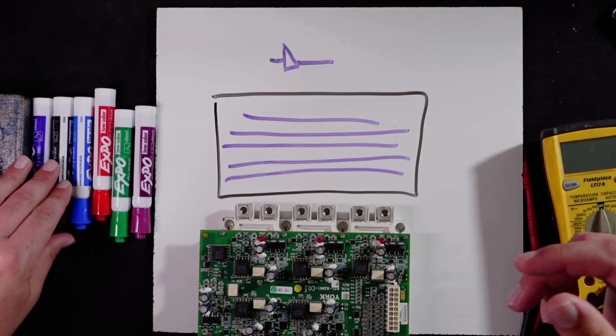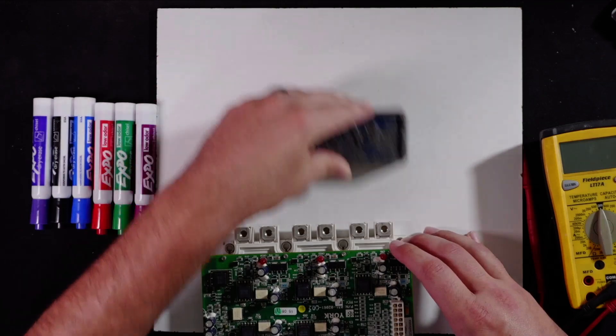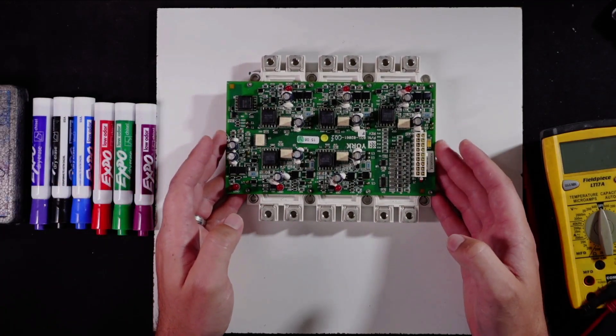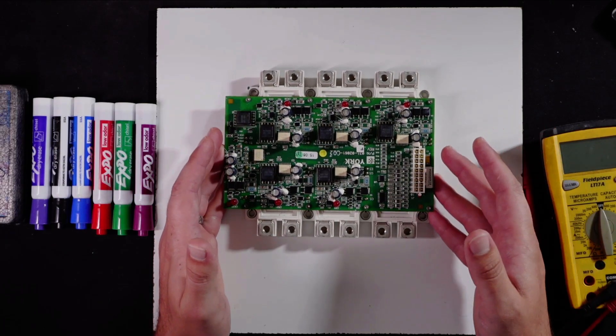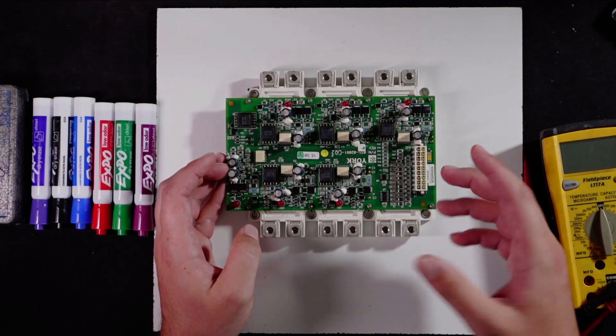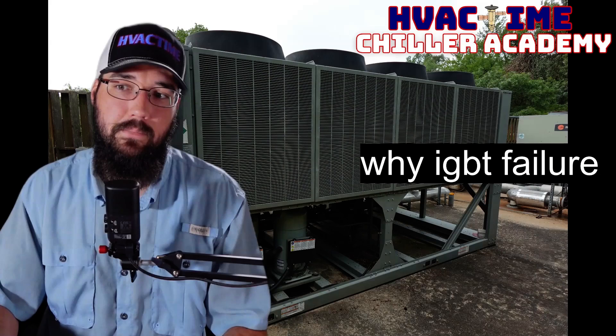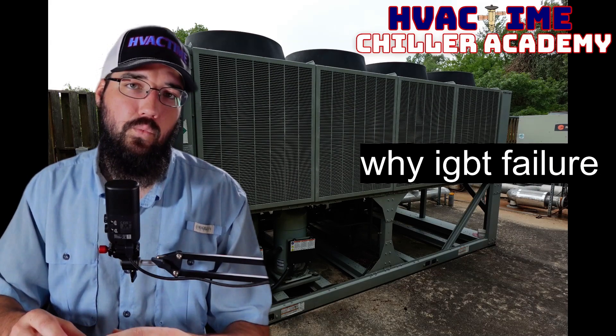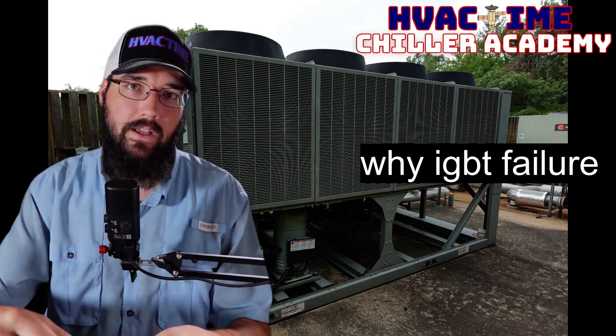So what that ends up leading to is you start having an actual gate failure where the gates themselves begin to just not process properly through them. One of the common signs I'll see of that is one, you could have a current motor current issue where you have motor current alarms. That could be because one of these gates is not outputting correctly. Another could be a grinding noise. So I've had it to where the compressor will sound like it has a bad bearing. When in reality, it's not a bad bearing. It's the IGBT.